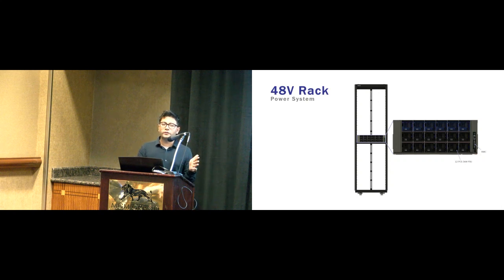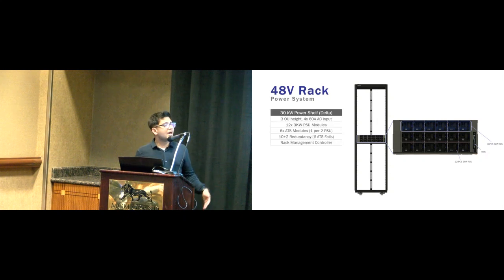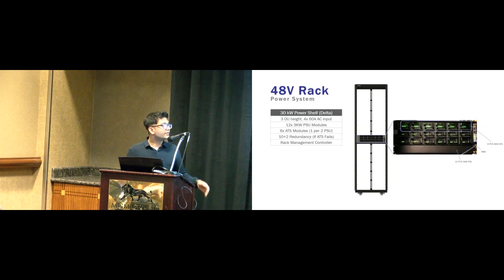Versus that, for Rackspace, and I know for a few other companies as well, it's important to have local rack level redundancy with an ATS. Those are the ATS modules. That solution didn't exist before, as far as I understand. So we partnered with Delta and came up with a power shelf with an integrated ATS. We have the shelf in our lab. That's a picture of the shelf in the lab, and it's up and running.